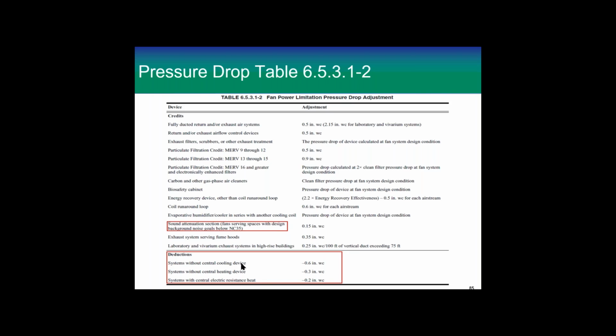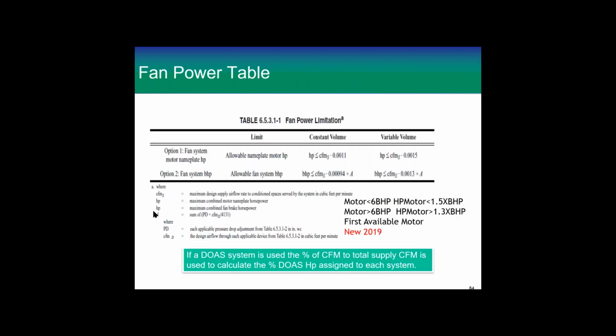You have a few that can give you credit. If you didn't have a cooling coil, you would actually get a penalty. But you add up your adjustments, and then you come over here and you take your PD, which is your adjustments, and you take the CFM through each one of those items, not your total, but what's through those items. And then you multiply your adjustment times your CFM through the item, divided by 4131, and you get your A. So you can do that however many times you have, sum them up, you get your A, and you use that right there.